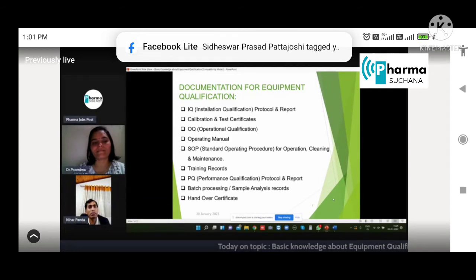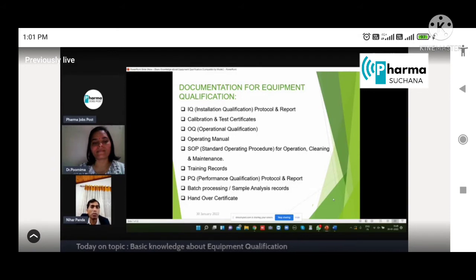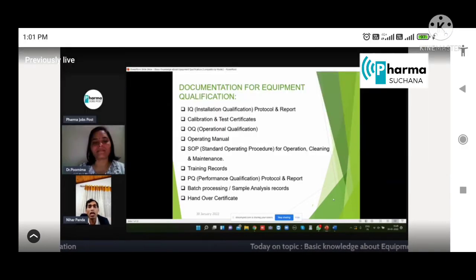Then there is the operating manual. We have to take the operating manual from the vendor, the manufacturer, and we have to prepare the standard operating procedure: how to operate, how to clean, and how to carry out the maintenance activity. We have to check during this OQ whether that SOP is complied with or whether any modification is needed. At this time, the SOP can be prepared in draft stage, and after completion of the OQ, we can go for the final SOP.